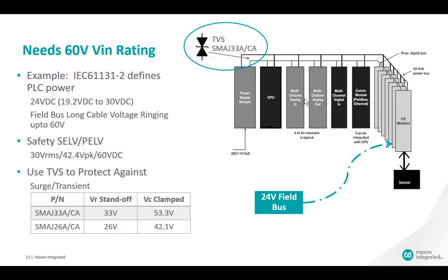In an industrial PLC system with power supply modules, CPU card, and I/O modules: when lightning strikes, there can be as much as 500 volts for tens of microseconds at the output of the power supply modules. For fieldbus systems with long cables, the voltage on the fieldbus can ring and double its input voltage — up to 60 volts. To protect against 500-volt transients and inductance ringing, a TVS is used, clamped across the output of the power modules. When selecting a TVS, there are two very important parameters to consider.